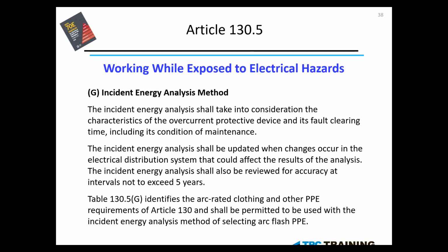Those labels, real quick, all arc flash analysis labels, all of your warning labels, need to be audited no more than 5 years apart. So if you've got labels that have been up for a while, I would take a look at the date on them or try to see if they still comply. 2 quick identifiers: if it has a hazard risk category or the prohibited approach boundary, those are 2 sure signs that that label probably needs to be replaced or updated, I should say.